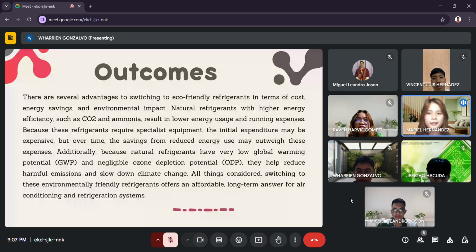For the outcomes, there are several advantages to switching to eco-friendly refrigerants in terms of cost, energy savings, and environmental impact. Natural refrigerants with higher energy efficiency, such as carbon dioxide and ammonia, result in lower energy usage and running expenses. Because these refrigerants require specialist equipment, the initial expenditure may be expensive, but over time, the savings from reduced energy use may outweigh these expenses. Additionally, because natural refrigerants have very low global warming potential, or GWP, and negligible ozone depletion potential, or ODP, they help reduce harmful emissions and slow down climate change. All things considered, switching to these environmentally friendly refrigerants offers an affordable, long-term answer for air conditioning and refrigeration systems.